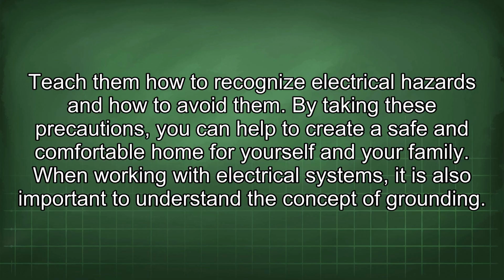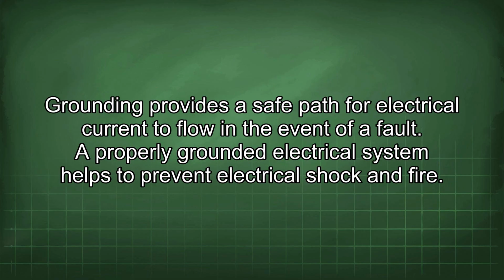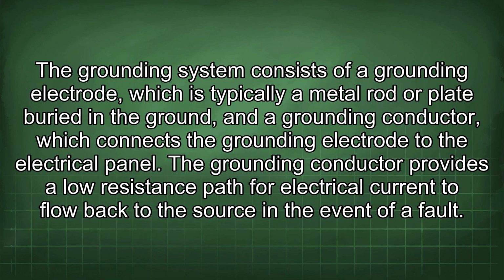When working with electrical systems, it is also important to understand the concept of grounding. Grounding provides a safe path for electrical current to flow in the event of a fault. A properly grounded electrical system helps to prevent electrical shock and fire. The grounding system consists of a grounding electrode, which is typically a metal rod or plate buried in the ground, and a grounding conductor which connects the grounding electrode to the electrical panel.